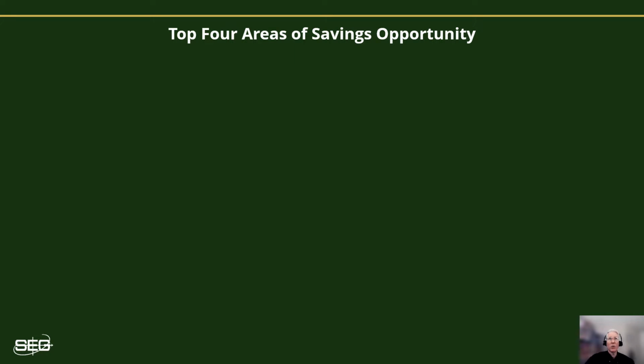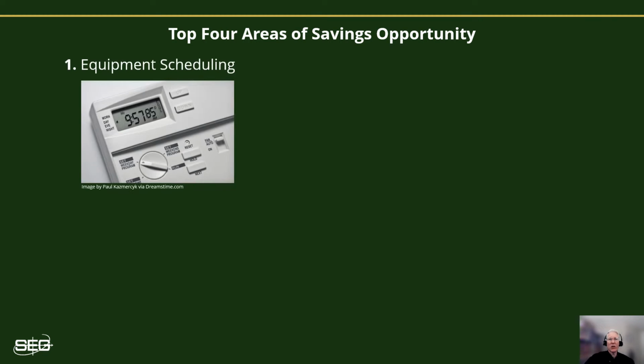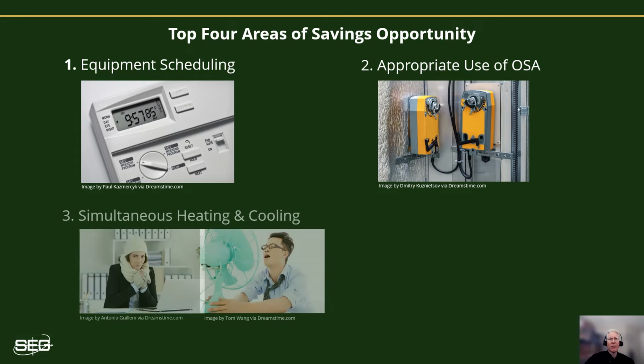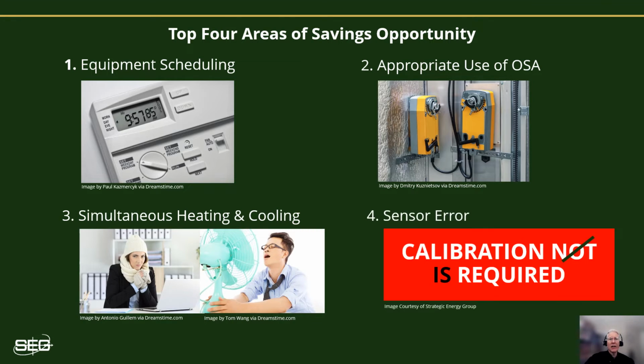These 4 items are widely recognized as top areas of savings opportunities in existing buildings: equipment scheduling, appropriate use of outside air, simultaneous heating and cooling, and sensor calibration. You might have noticed that all 4 of these involve only the HVAC systems. Well, while lighting systems oftentimes have significant energy savings opportunities, we find most lighting issues and their opportunities tend to be more easily recognized and therefore more readily addressed. Yet the HVAC systems generally exist out of sight and tend to be complicated and more difficult to understand. As a result, HVAC savings opportunities are largely unrecognized and frequently overlooked.